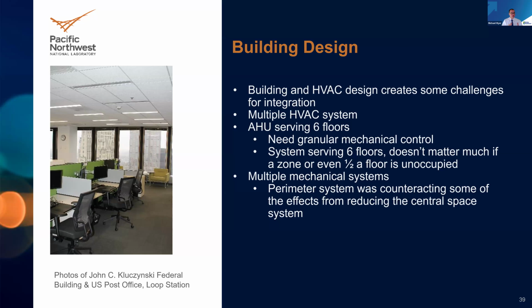Why that matters is if you're trying to use an occupancy system to communicate with your mechanical to start doing setbacks, if your air handler is serving multiple floors, it doesn't really matter. You can't, unless every floor is empty - and then is the occupancy control really working, or should it just be a schedule-based approach?